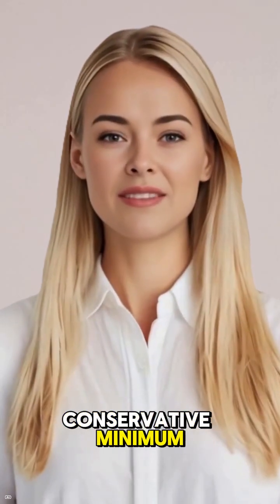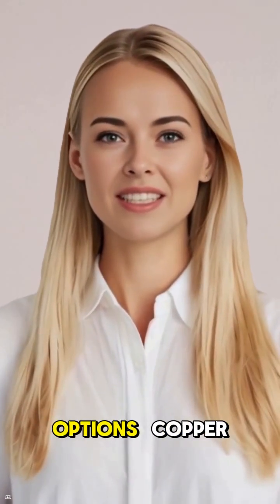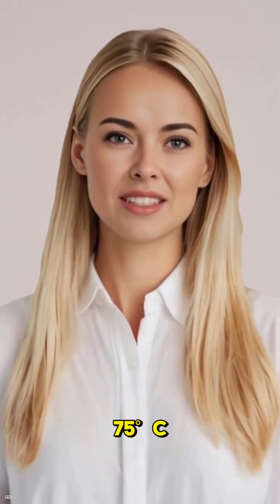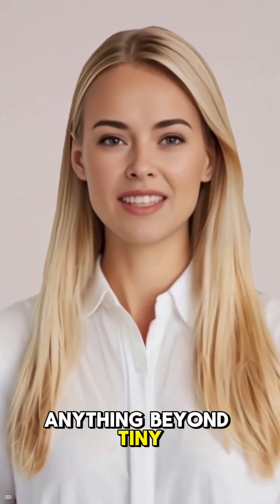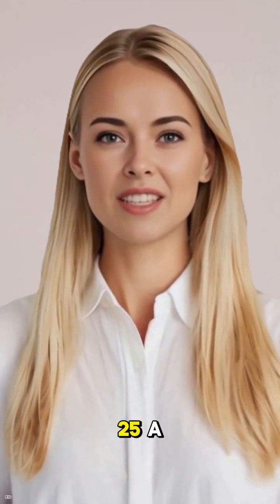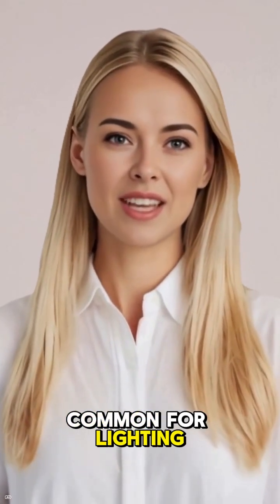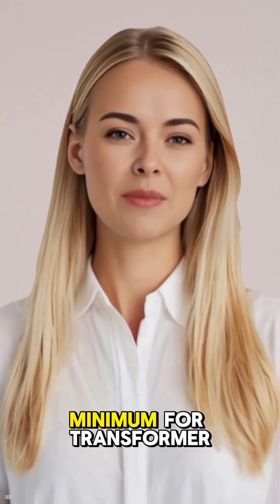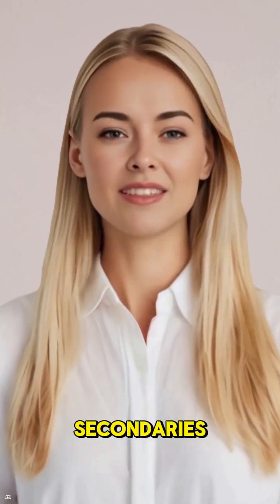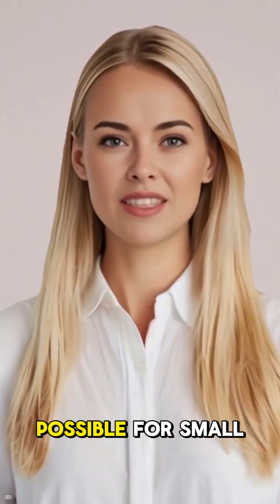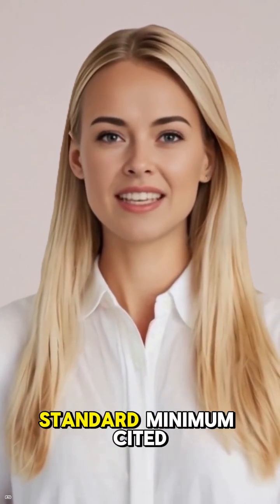the conservative minimum. Quick comparison of options: copper, 75 degrees Celsius ampacity from Table 2. Number 14, 20A, too small for anything beyond tiny control transformers. Number 12, 25A, is common for lighting and general branch circuits, but not a typical minimum for transformer secondaries. Number 8, 50A, possible for small transformers, but not the standard minimum cited.